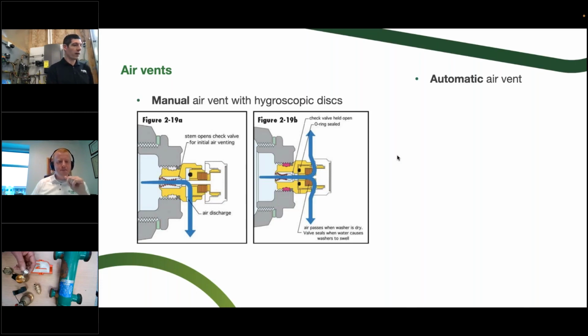So let's talk about radiators, maybe specifically. We've got a demo over on the shop cam here. We've got 2 different options for our manual air vent that has the hygroscopic discs inside of it. So you can kind of see into the belly of it right there. 2 different choices. If you use a little Tupperware or whatever you use to purge a radiator, you can do that with the manual setting, and then you can turn it so it's in automatic when you're all done with that.